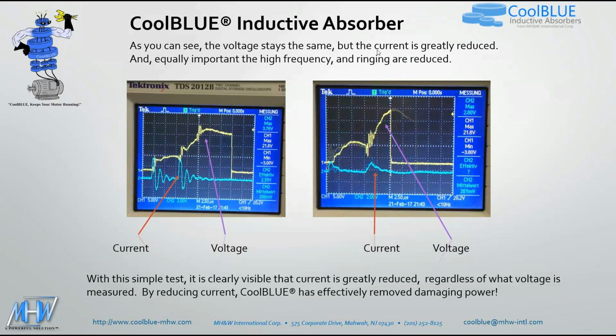As you can see, the voltage stays the same. This is just a zoomed in, more detailed view of the previous slide. But the current is greatly reduced. And equally important, the high frequency and ringing are reduced. So here's your voltage. Obviously, there's some noise going on with the voltage wave shape right there, right there, and right there. And you see what happens. It causes these high frequency current spikes to happen. We put CoolBLUE on, and at those same transitions, you'll notice how those high frequency current peaks are greatly reduced.